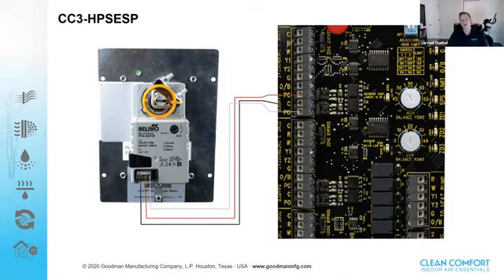On the flip side of that, a 2-wire motor has a spring that it works against. So when we put 24 volts to a 2-wire motor, it just powers one way. Normally it's power open, spring close, or power close, spring open. What that means is that motor has to meet and exceed the resistance of that spring all the way until it meets the end of its travel.